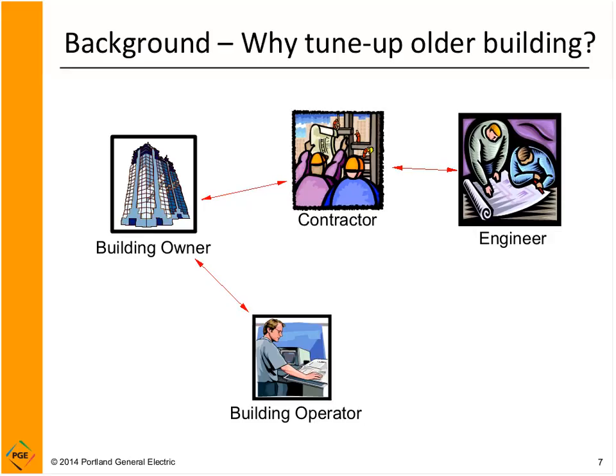But maybe you can more effectively and efficiently satisfy the customer by changing airflow rates in air handlers rather than putting a whole lot more load on your chiller. So that's the basics of tune-up and commissioning: am I operating my systems the way they were intended and at the best efficiency possible?